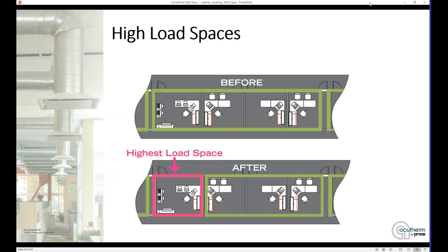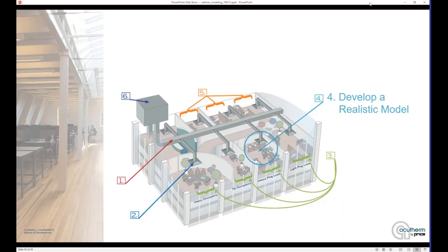Having a system that can deal with that, like a Thermafuser diffuser system, is very important. But also modeling it to show that it's working is very important, making sure that averaging doesn't dilute those high-load spaces and blur them into an average load across the full space. In our model, we had four offices grouped together, but one office has been noted as a high-load space — for whatever reason, the user there is running multiple PCs, multiple printers, plotters — a higher load in that space. So we're just going to model that separately to capture those loads correctly.